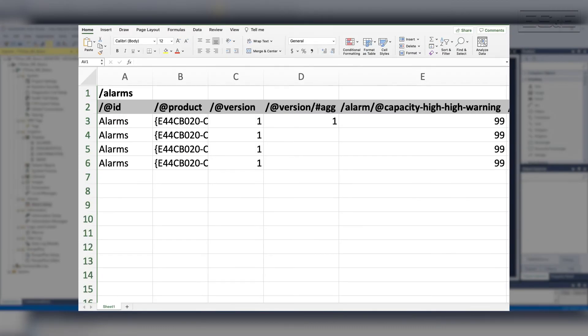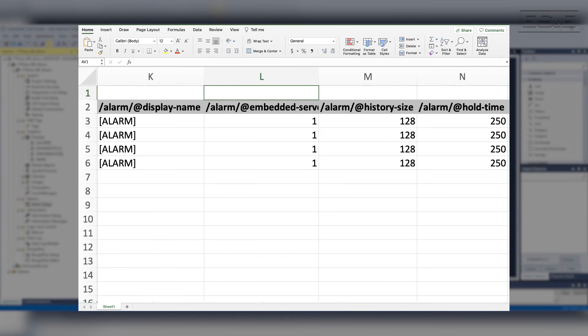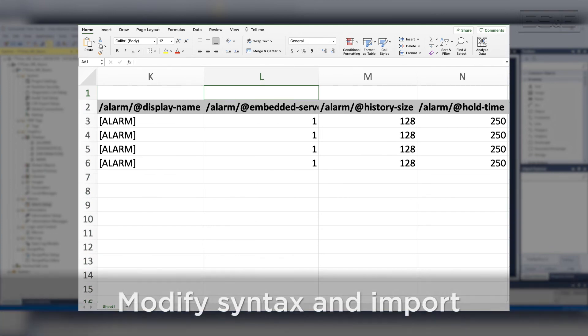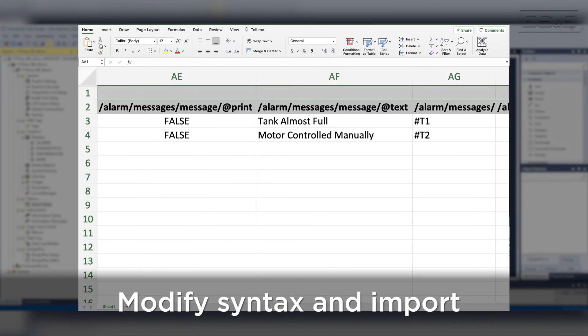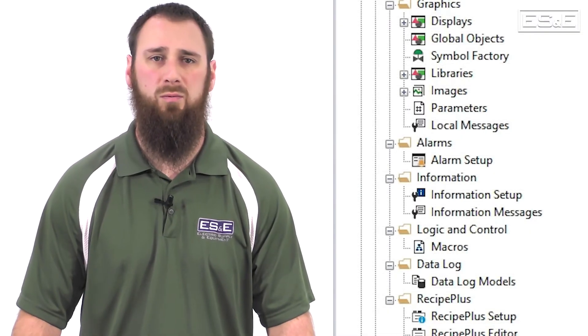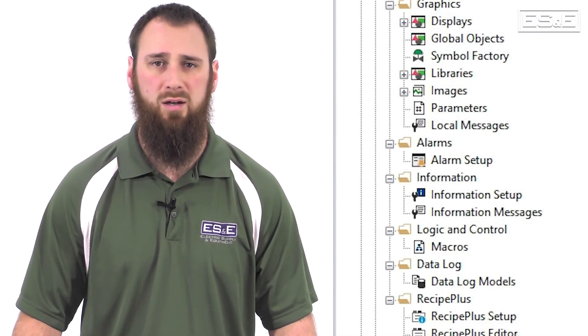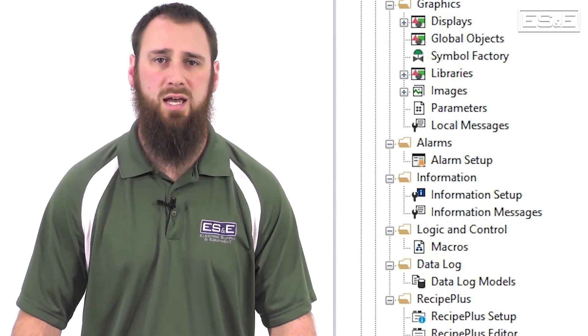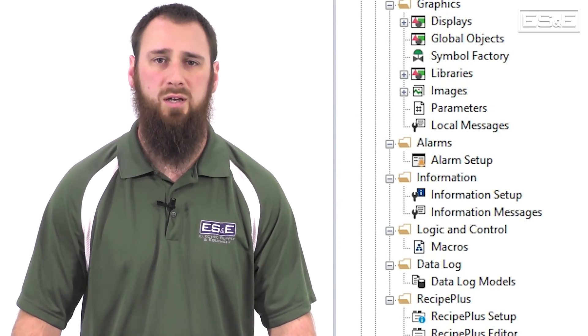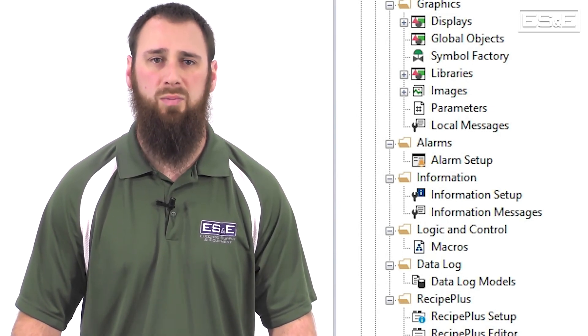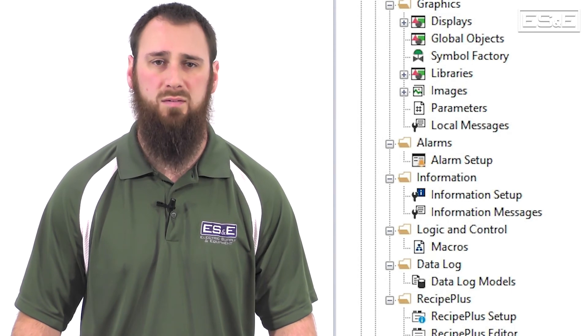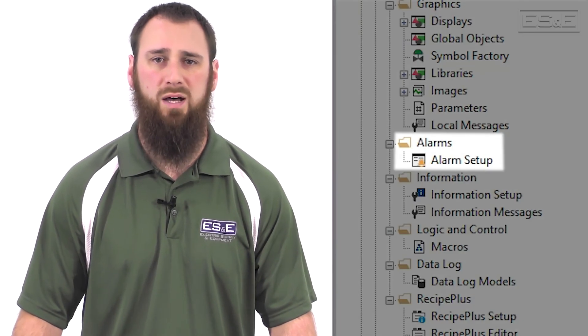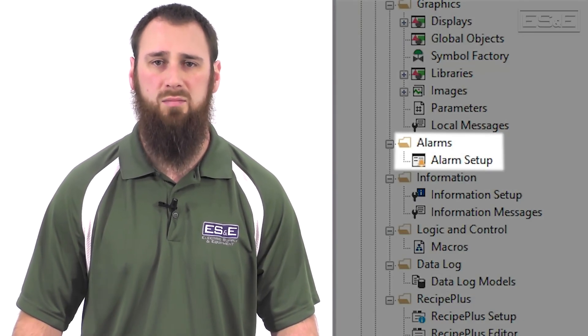Once you create the alarm, it will give you the proper syntax so you can quickly modify it all in Excel and then import the modifications back into the project. For people that want to utilize tag-based alarming, you can access those through the extended tag properties, but still require you to set up all the tags individually in the alarm setup file inside the ME project.